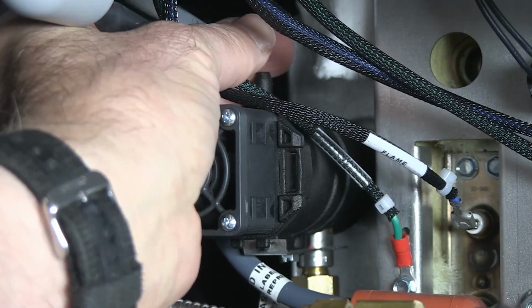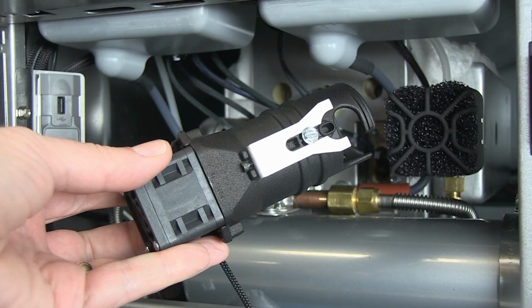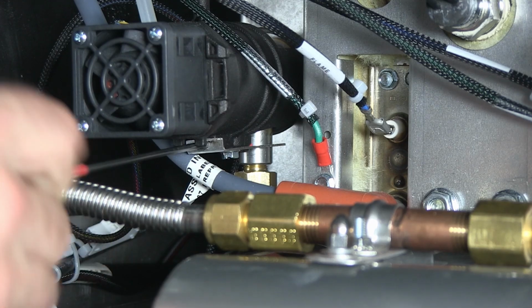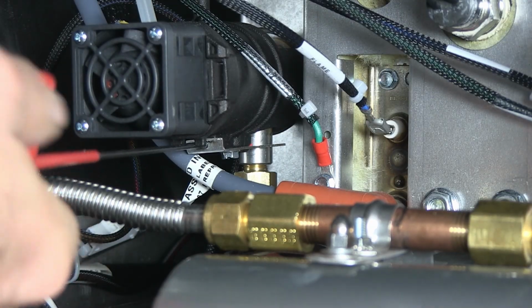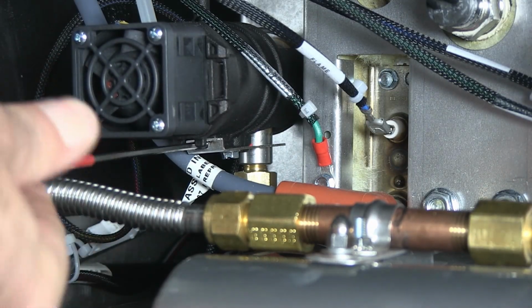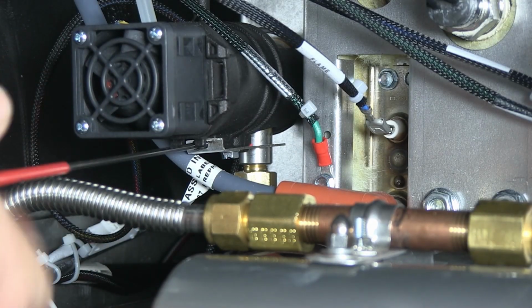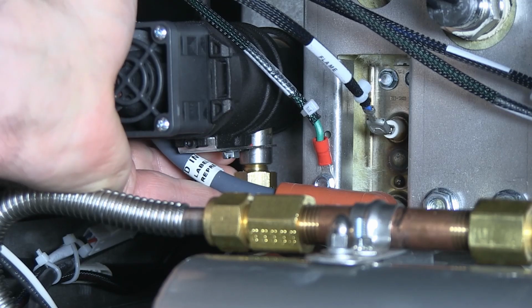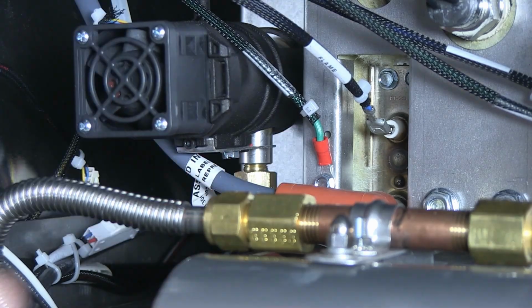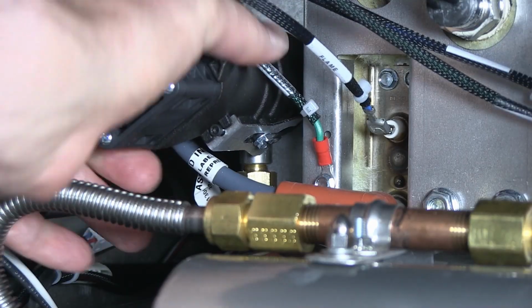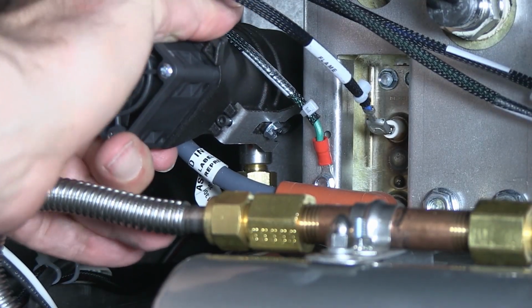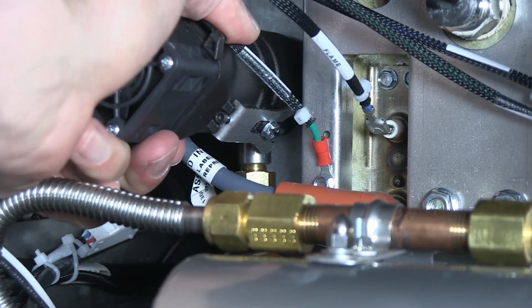Remove the pressure switch hose. The fan assembly, shown here removed, has a notch and a bracket that secure it to the burner. The bracket must be pulled forward and the fan assembly rotated to clear the notch during removal. Loosen the Allen screw below the fan. Do not remove the Allen screw completely. Loosening pulls the split bracket at the rear of the fan forward, clearing the gas line. After loosening, pull the bracket forward. Rotate the fan assembly counterclockwise to align the assembly notch with the gas line. Pull firmly forward. The assembly is held internally with O-rings.